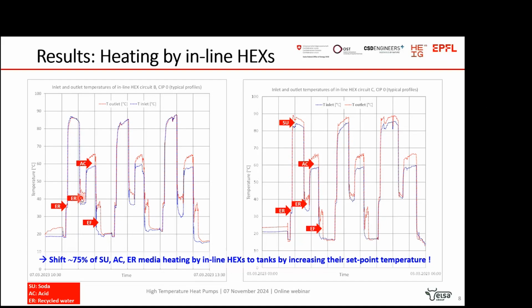The problem at ELSA is that we cannot retrofit the 37 steam heated heat exchangers, there is no place for that, and it would be too costly. So one solution we envisaged was to shift a big part of the heat presently supplied by the inline heat exchanger to the tanks, by optimizing and increasing their set point temperature. Of course we cannot do 100% because the circuits probably have different set points, but we can at least shift a big part of the heating currently achieved by the inline heat exchanger to the tanks.